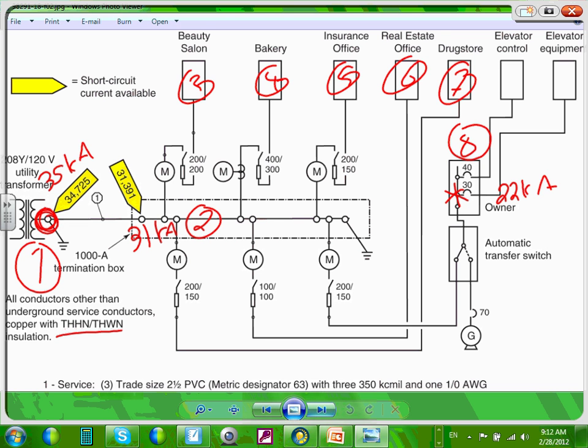So this panel right here could be rated 22 kiloamps, withstand and interrupting. This one, because it's closer, or because it's bigger, could be rated for 35 kiloamps, based on the available short circuit on it. When you use the software, we're going to build a riser in the PTW software that we have, exactly like you do in Revit, and we're going to run the analysis on it. And the software will assign a value right next to every panel in your building.